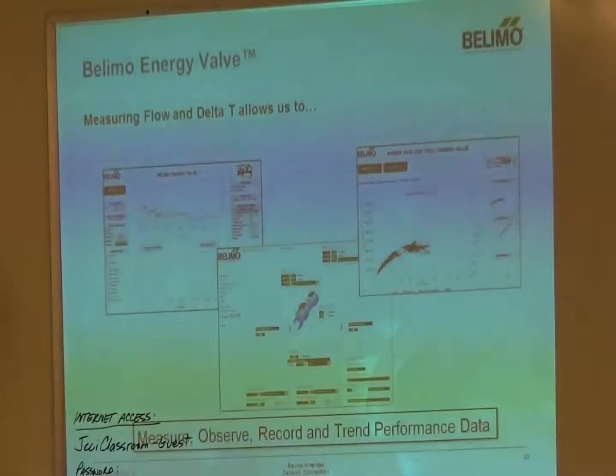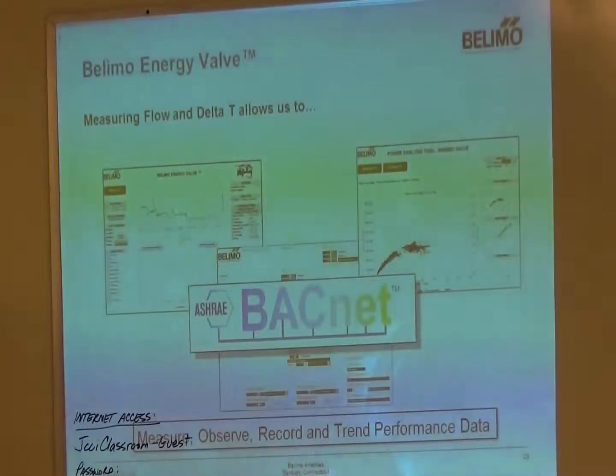So with this product, we're able to measure flow and delta T, which allows us to measure, observe, record, and trend performance data. All that can be sent back to your automation system via BACnet. And you can see on the back of the actuator here, we have a plug where you can plug in your Cat 5 cable. Now you can also just bring your laptop up and connect the Cat 5 cable right to the valve itself. If you don't have a Cat 5 drop near where the valve is going to be, which does happen quite often, if you want to read the information off the valve, just bring your laptop, Cat 5 cable, plug in the IP address, and you can read the information right there.